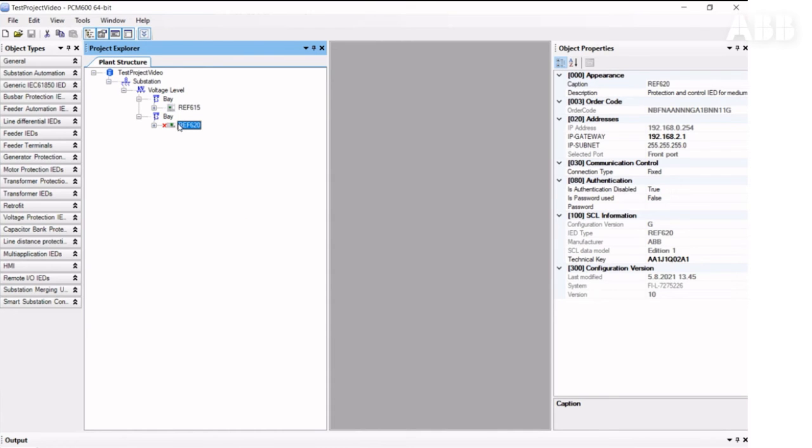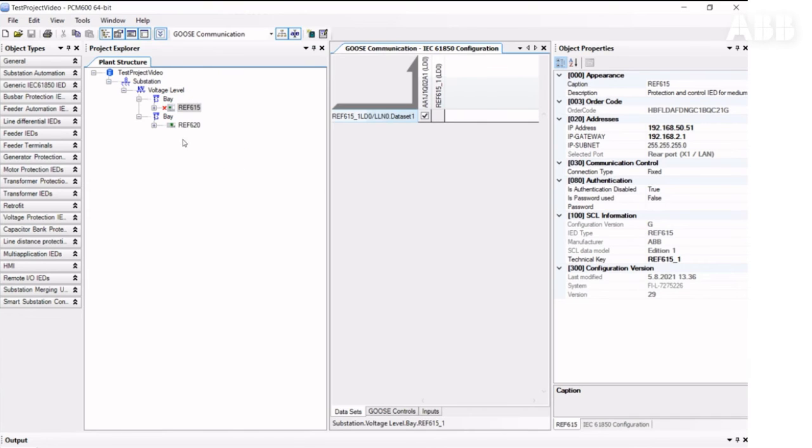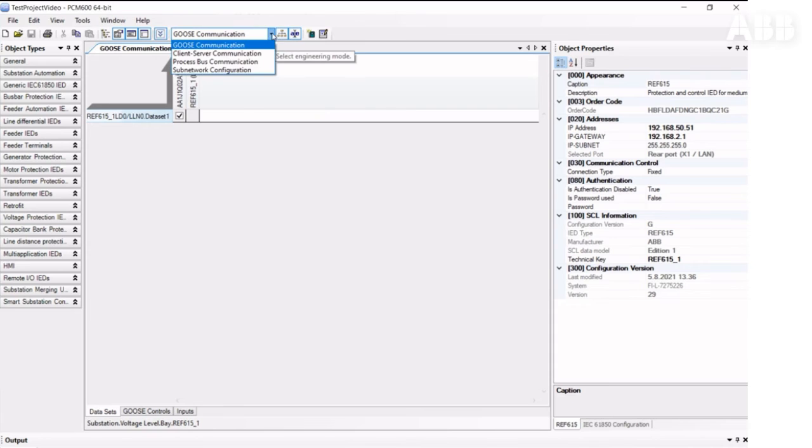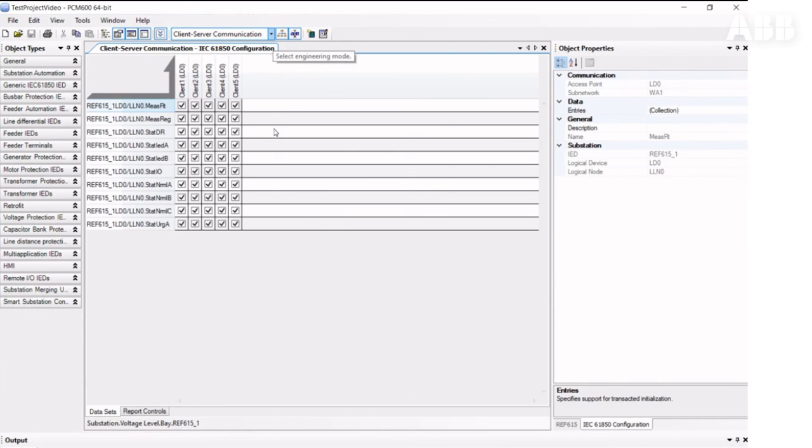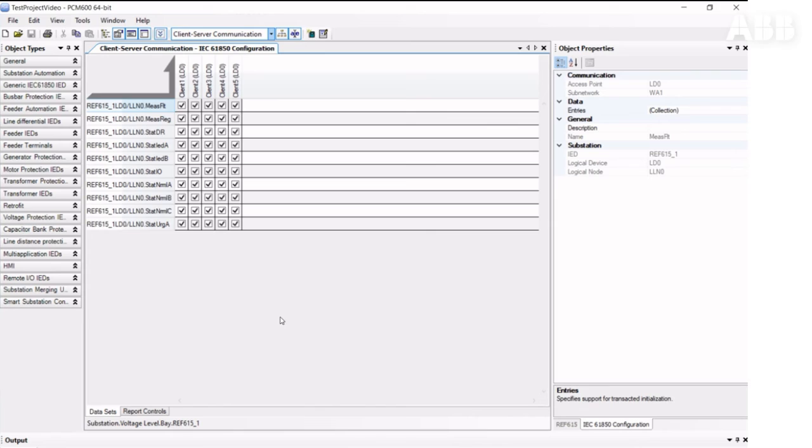We have not gone through one aspect of IEC-61850 configuration, which is client-server or vertical communication. When you create the configuration in PCM600, it automatically creates datasets with most of the signals within them. And if you create the configuration from scratch, these datasets are not assigned to the clients.